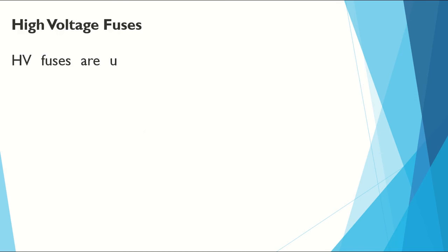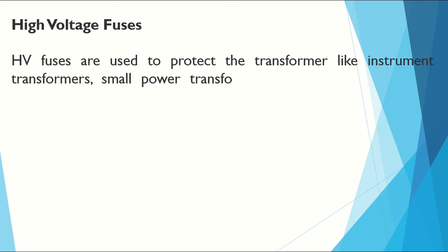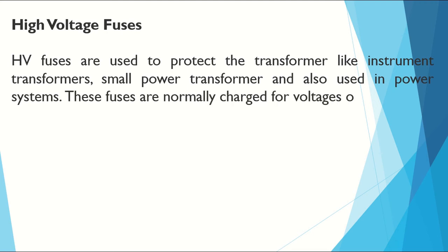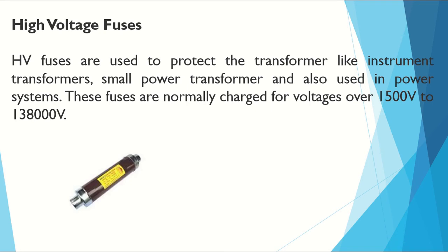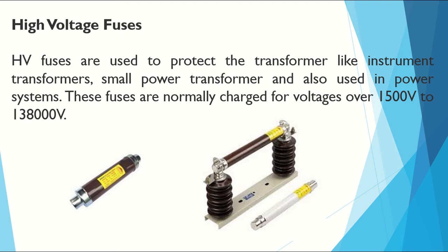High voltage fuses are used to protect transformers such as instrument transformers and small power transformers, and also used in power systems. These fuses are normally rated for voltages over 1500 volts up to 138,000 volts. They can be found in poles, transformer structures, and substations, and come in sand color and white color.